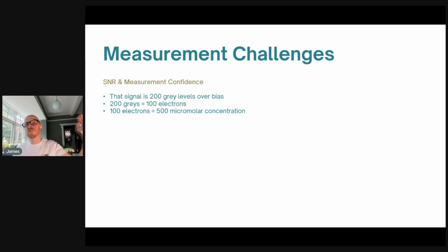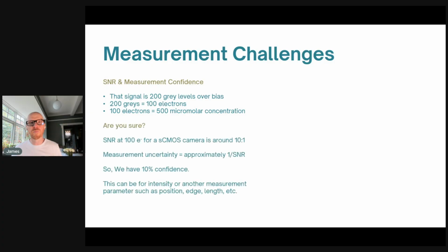What about measurement challenges? I made up some numbers. I have 200 gray levels above bias, which means I have 100 electrons of signal in the world of this camera. 100 electrons of signal equals 500 micromolar of concentration. All fantasy in James's world. But what I want you to do is connect the number of electrons to a measurement that you want to make. Am I sure? The problem with having signal to noise of 100 electrons is I'm roughly going to get a 10 to 1 signal to noise, and I have some uncertainty in my measurement. So 1 divided by the signal to noise is my measurement uncertainty. So I have 10% confidence or 10% uncertainty in the measurement.